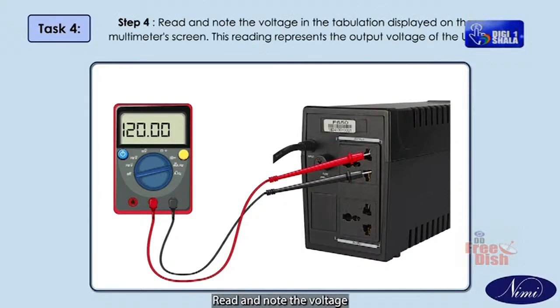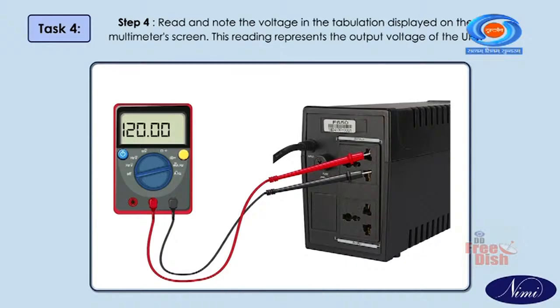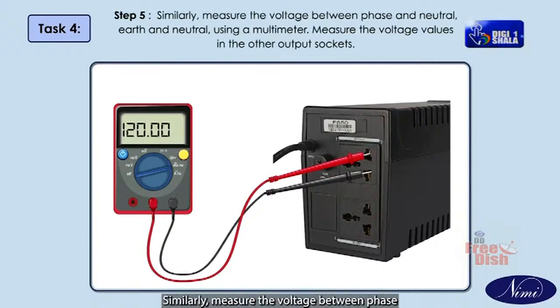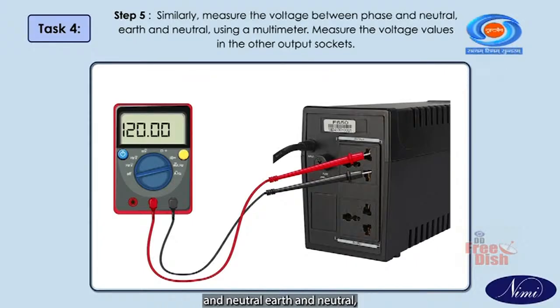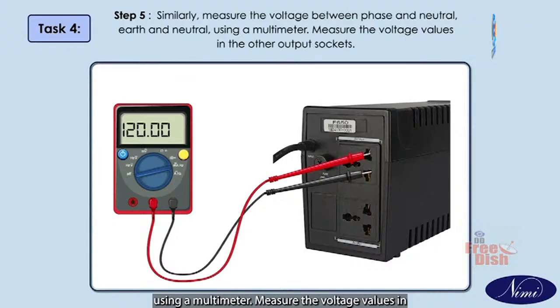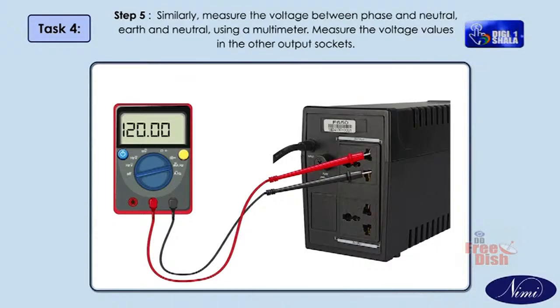Step 4. Read and note the voltage in the tabulation displayed on the multimeter screen. This reading represents the output voltage of the UPS. Step 5. Similarly, measure the voltage between phase and neutral, earth and neutral using a multimeter. Measure the voltage values in the other output sockets.